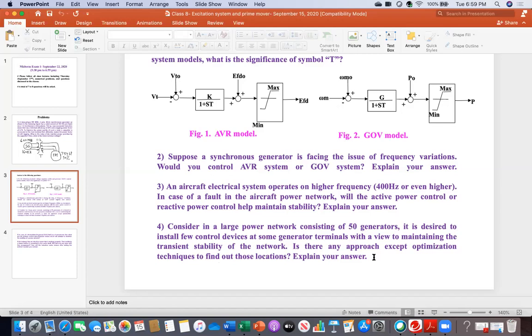Coherency, maybe. Coherency, right. A couple of classes back I mentioned the concept of coherency. It means you look at the torque angle or rotor angle of those generators, how they behave, and then figure it out. You can cluster them into groups—maybe 10 groups—and for each group of 5 or 6 generators, you put one control device. In that way, you reduce the number of control devices and reduce the cost.